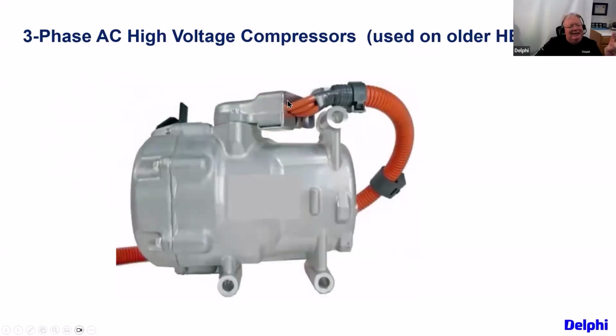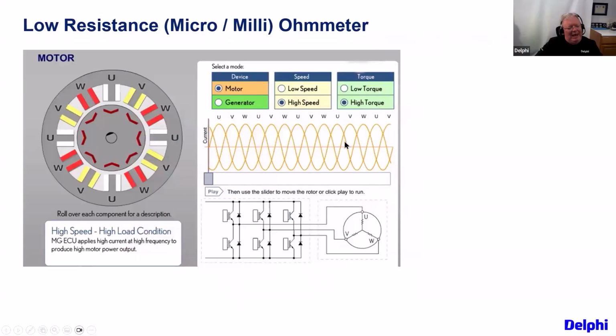However, these wires are insulated and shielded. Current clamps are useless unless you make jumpers, which is a little bit dangerous. You can do it, but it's for the artist who knows how to do this. You can make jumpers that don't have that shielding underneath the insulation, but these are special wires that are double electrically insulated and EMI shielded, so the inductive amp clamps won't work. So you really can't see this waveform.